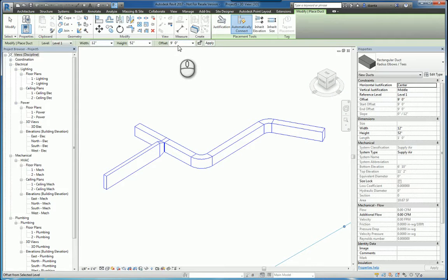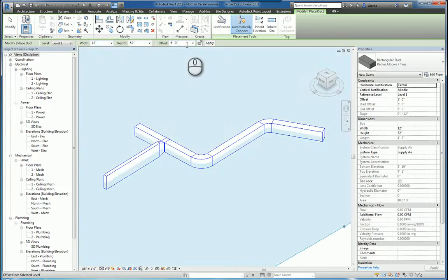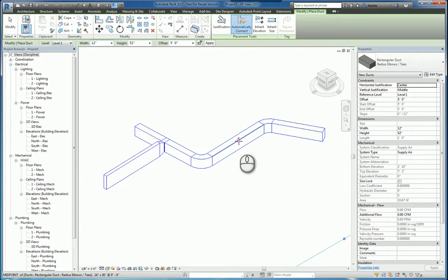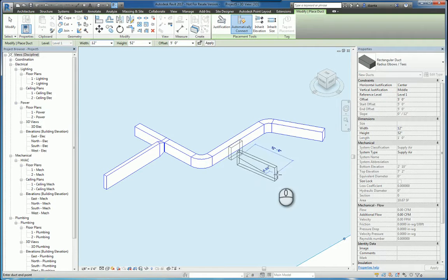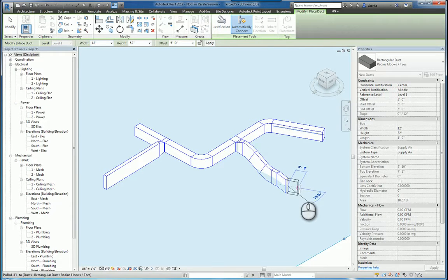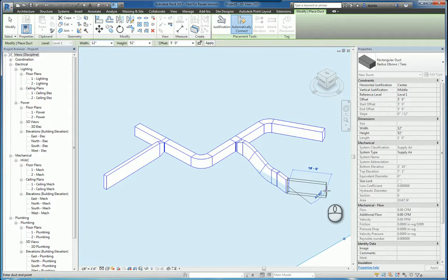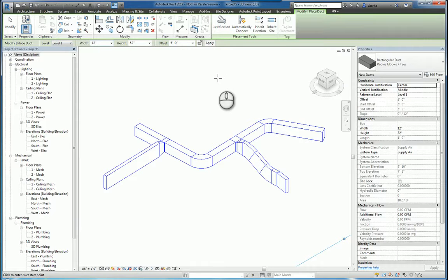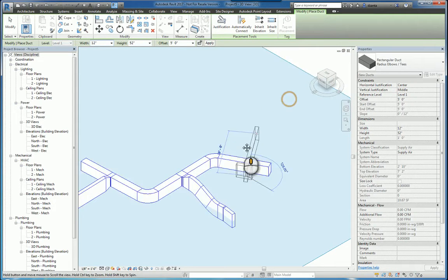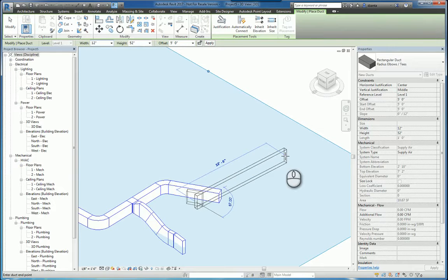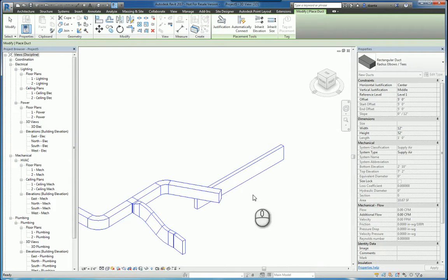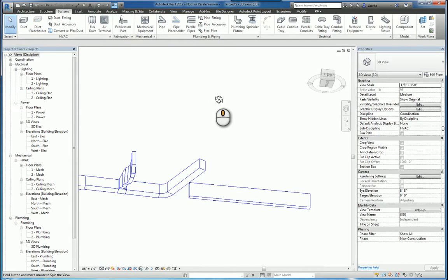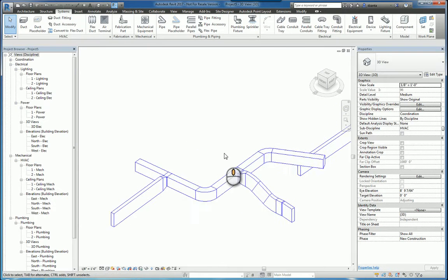If I use the same command, same settings, but I change my offset height to something else, say 5 feet, and I leave automatic connect turned on, as I select the existing ductwork to connect into, that automatic connect feature will still let it connect, but it will also make the adjustment for the necessary fittings to make it connect. If I uncheck automatically connect, and I try to connect to this piece of ductwork, it's going to draw it, but it's not going to connect it, as you can see here. So that's what the automatic connect feature is for.